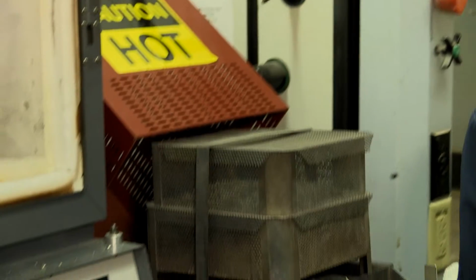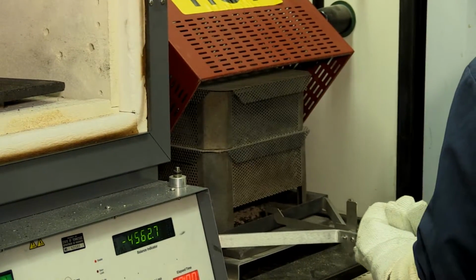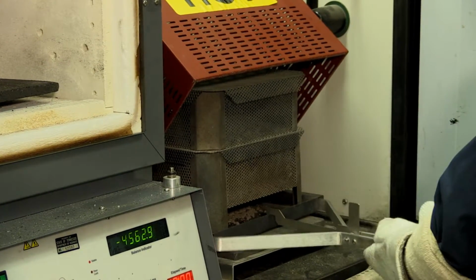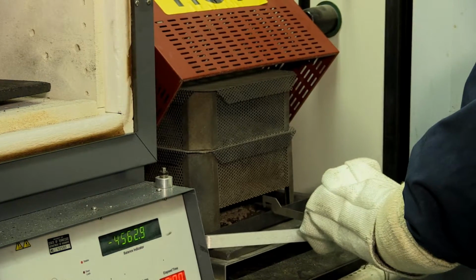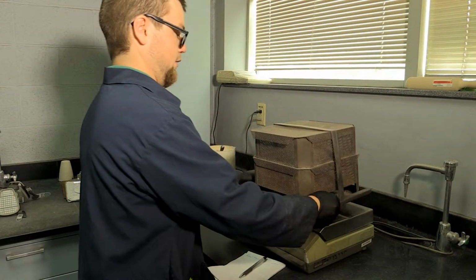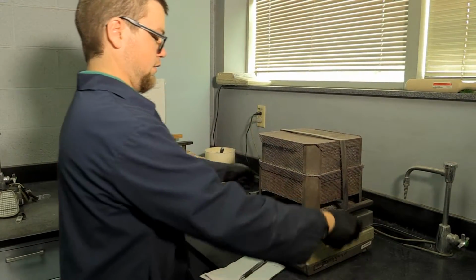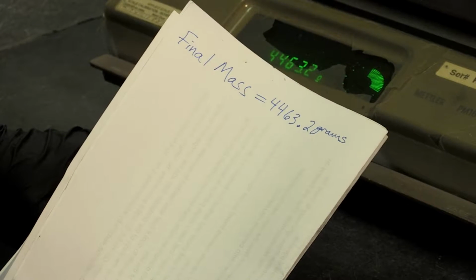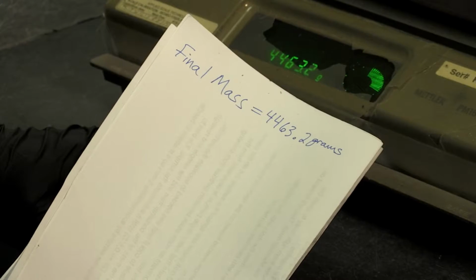Repeat this process for an additional sample. Once 2 samples are completed, a calibration factor can be determined. Enter the 3rd sample mass and adjust the calibration factor according to the findings from the first 2 tests. Then run the 3rd ignition test.